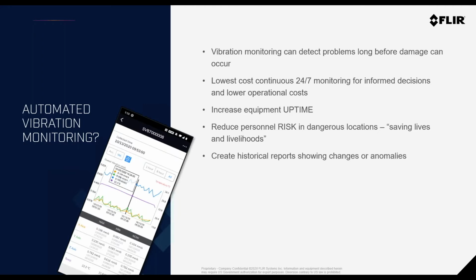On the FLIR side, FLIR also recently just launched a new product. We call this our SV87. This product is going to be used to monitor, to do continuous monitoring of vibration. So this is something you can set up, and then it's kind of one of those set it and forget it things. We have software that comes with it that can alert you when your system is out of line. You're going to put something like this on your critical equipment. Again, maybe the most expensive equipment, or the equipment that gets used the most often, or the equipment that produces the most amount of goods.